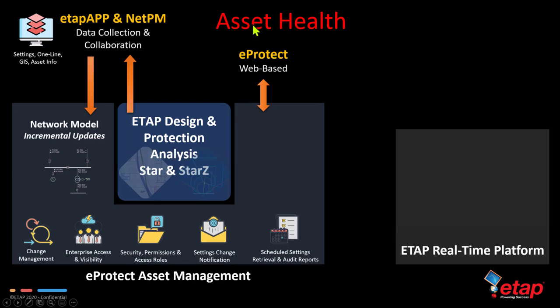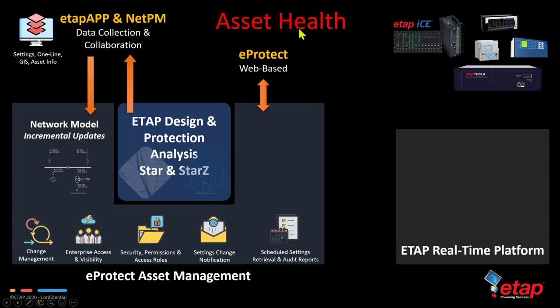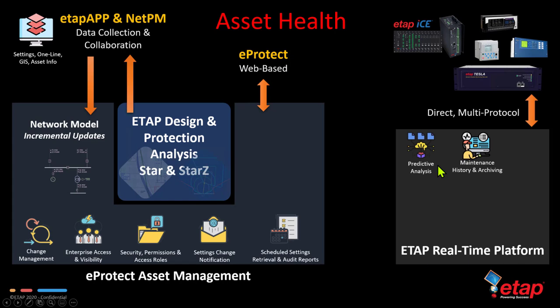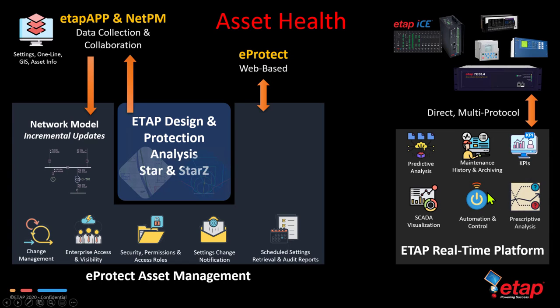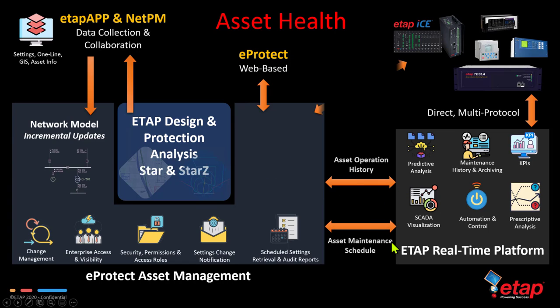eProtect can also be used for visualizing asset health information, such as key performance indicators from ETAP ICE, ETAP Tesla dynamic disturbance recorders, and of course other IEDs and digital relays. Using direct multi-protocol communication, we can use the ETAP real-time platform for predictive analysis, maintenance history and archiving, generating KPIs, performing SCADA visualization, automation and control, and of course prescriptive analysis. The asset operation history can then be synchronized with the eProtect database as well as the asset maintenance schedule.